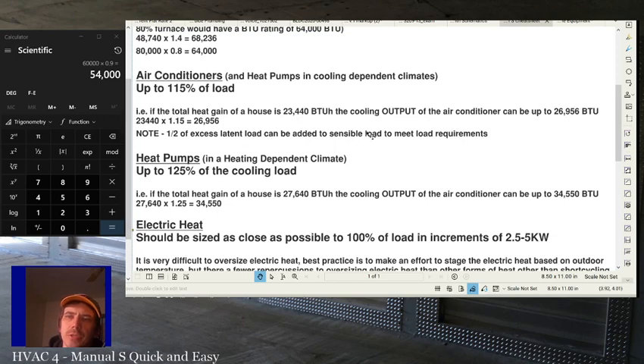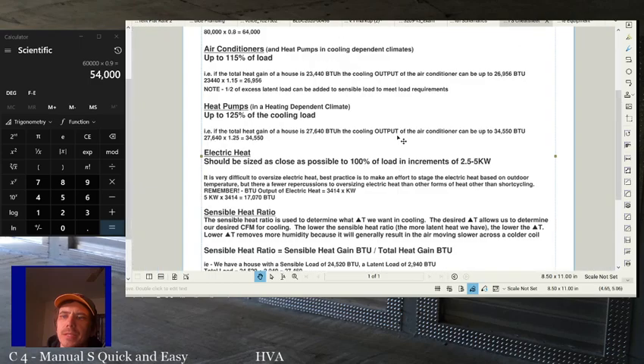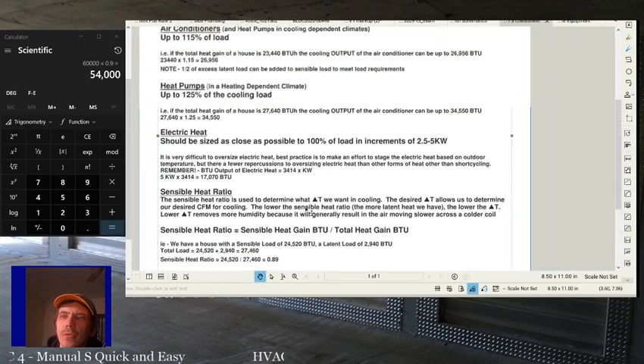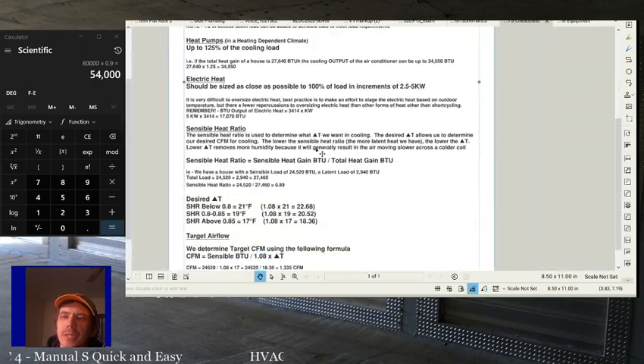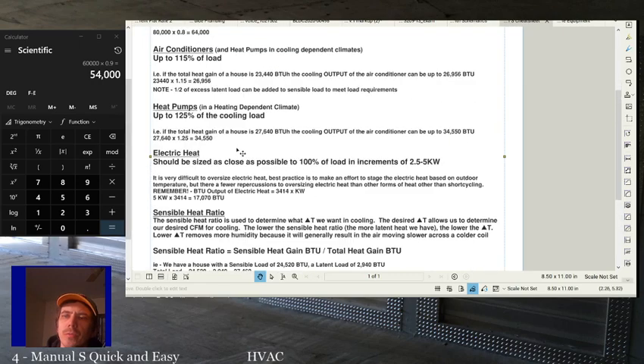That note's there just so you have that note, because that 26,956 BTU air conditioner, right? Whatever air conditioner you pick needs to be able to meet the sensible and the latent load requirements independently. So we'll talk about it when we get to the heat pump example, because down at the bottom I've got those things mapped out separately, or when we get to sensible heat ratio, we'll talk about that.